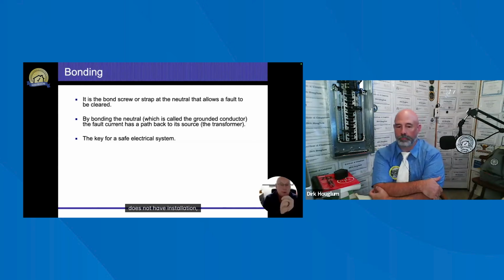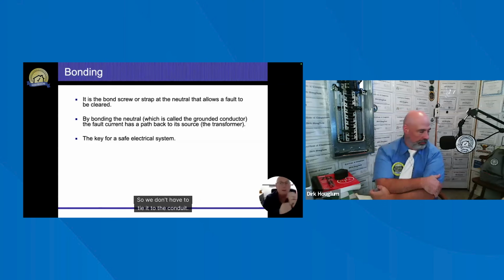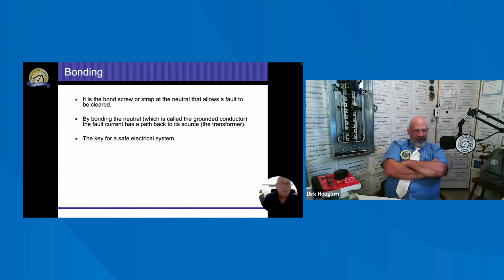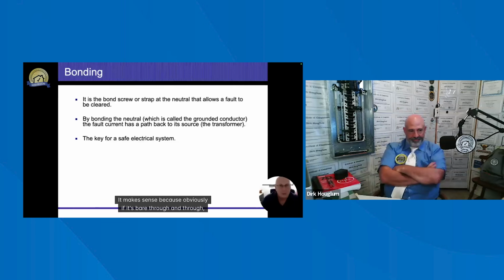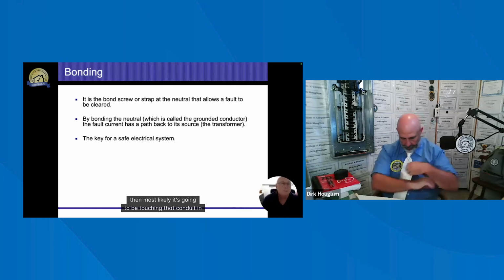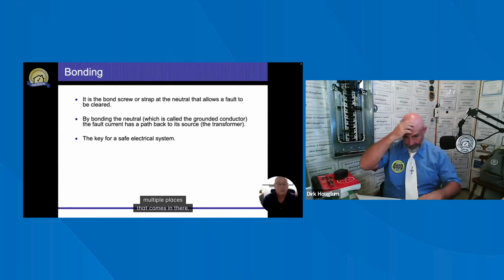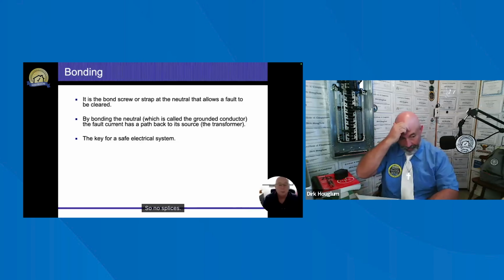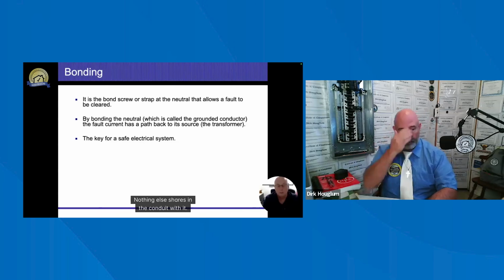If it does not have insulation, so it's a bare conductor for the GEC, and you will run into those, those are not required to have a mechanical or a metal connection at each end, so we don't have to tie it to the conduit. It makes sense because obviously if it's bare through and through, then most likely it's going to be touching that conduit in multiple places that comes in there. So no splices, number 6 or number 2, 150 amps is my line in the sand. Nothing else shares in the conduit with it.